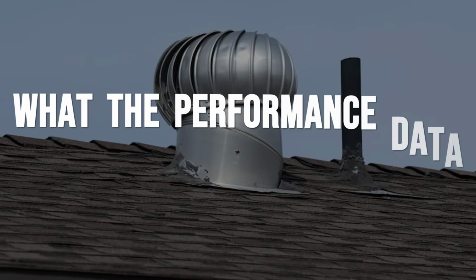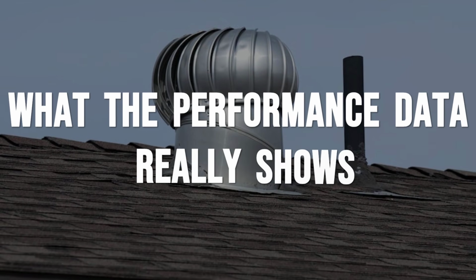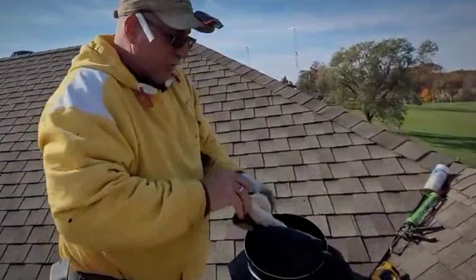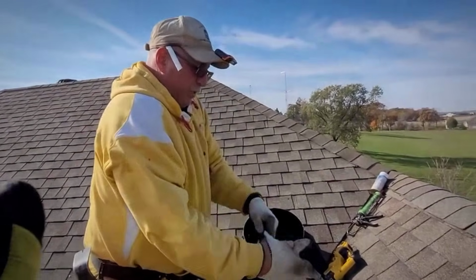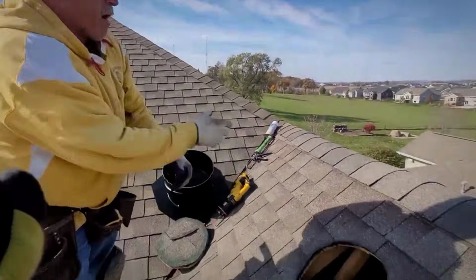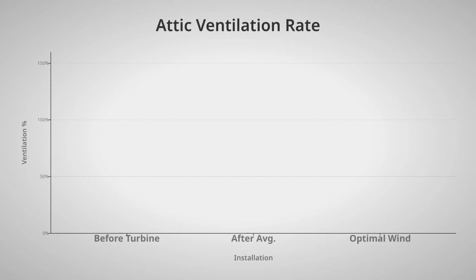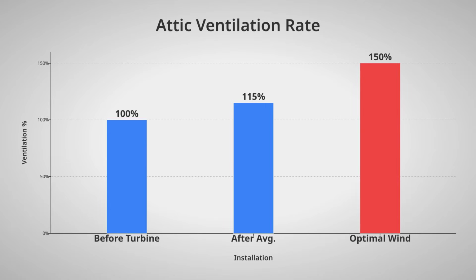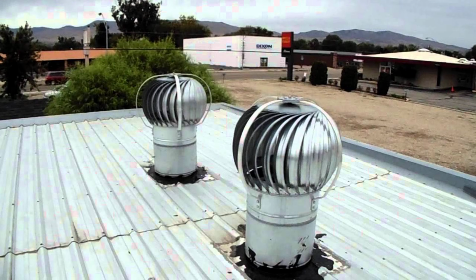And this straightforward design has proven to be genuinely effective. A study by the Air Infiltration and Ventilation Center found that installing a turbine ventilator increased attic ventilation rates by an average of 15% across a full year, with improvements reaching up to 50% when wind approached the unit from its optimal direction.